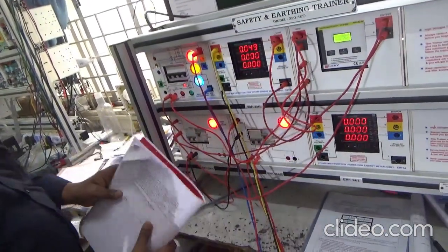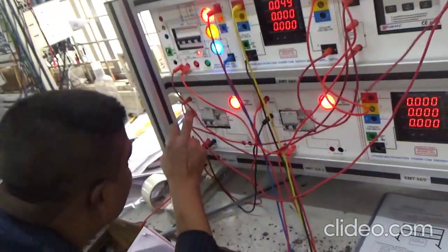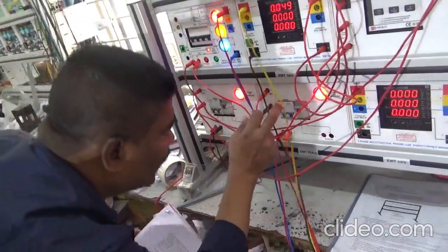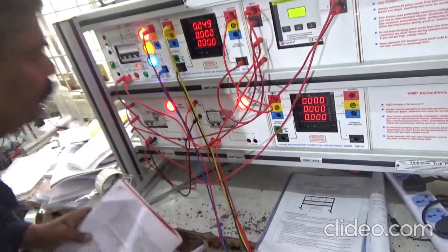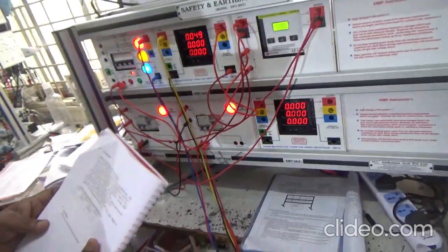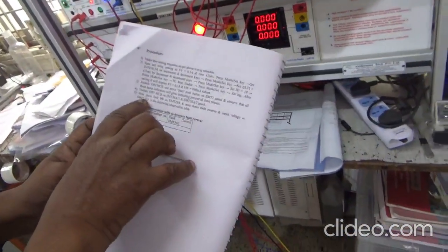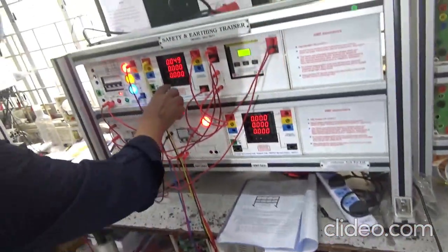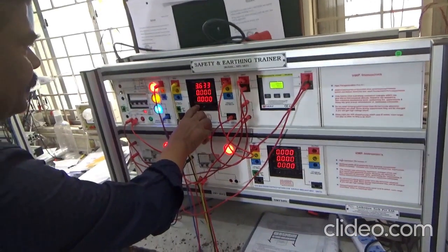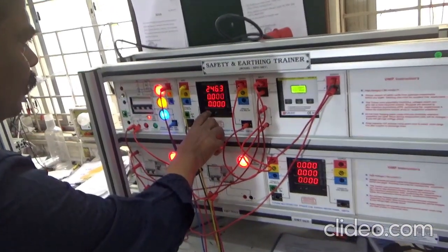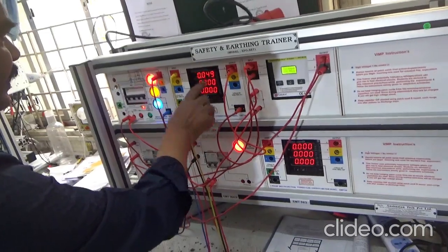So there will be indicators on these two, earth leakage circuit breaker panel 1 and earth leakage circuit breaker panel 2. So there will be power indicator. Now they have written the last line, 5th. Now press fault push button on EMT29A. So basically this is EMT29A. I'll have to press it till here. A fault current will flow. I'll make this one to current. This is the voltage. Voltage is completed. I'll make it to current. We'll check the current also.